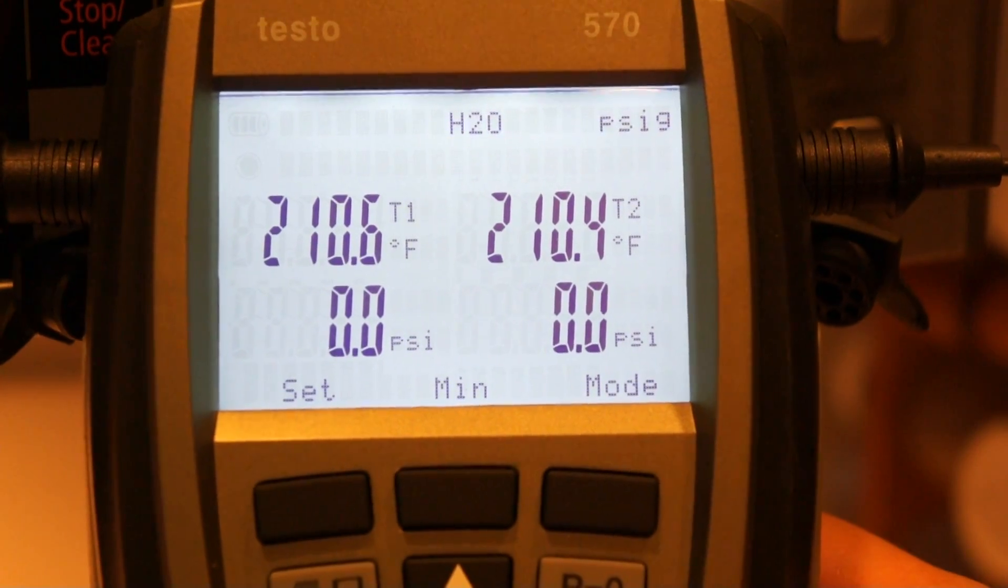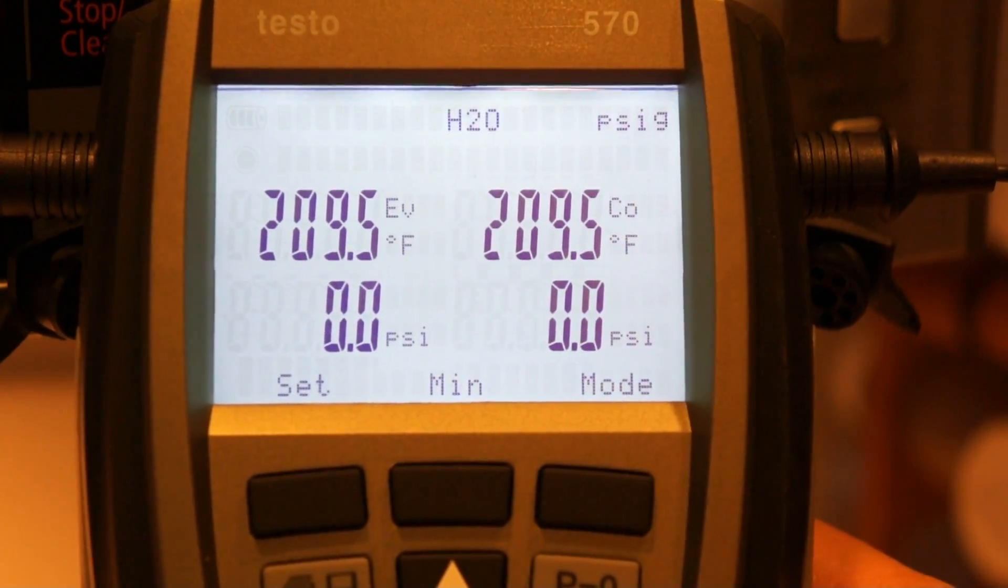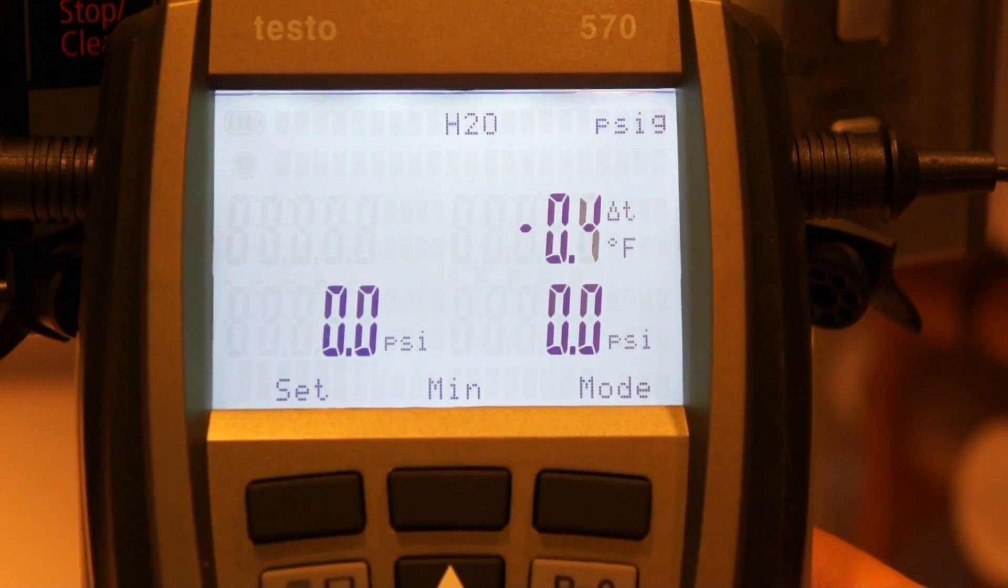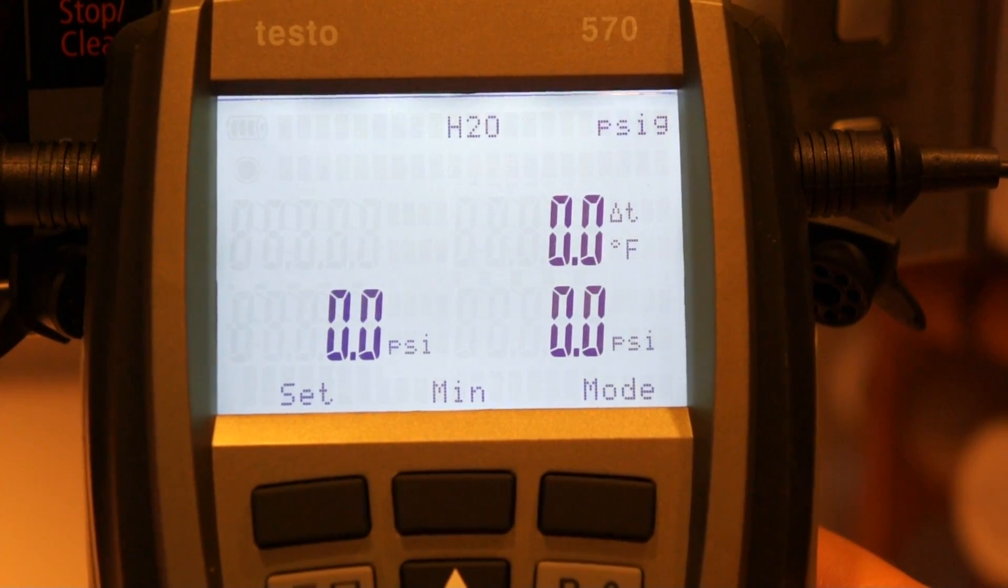So T1 is measuring 210.6, 210.4, and then, etc. Saturation temp, 209.5. And then the temperature difference between the two probes is about two tenths of a degree to zero, somewhere in there.